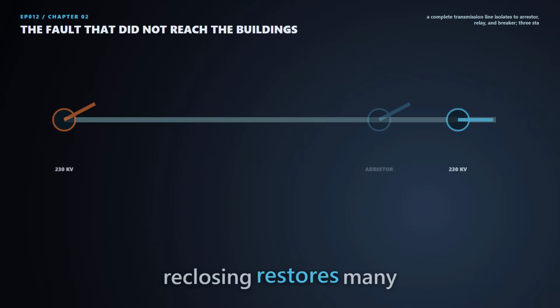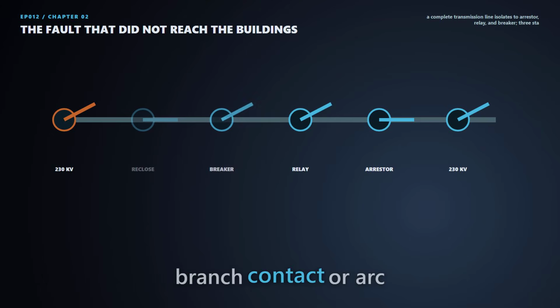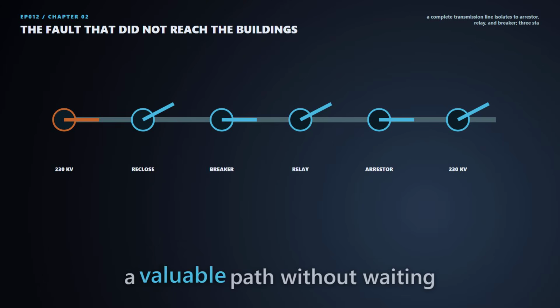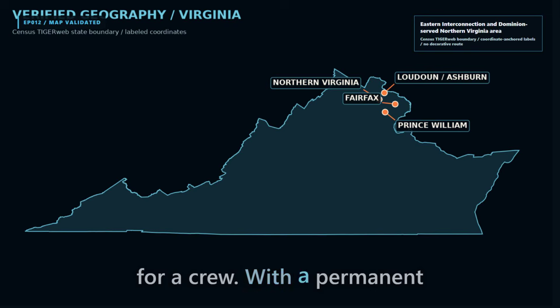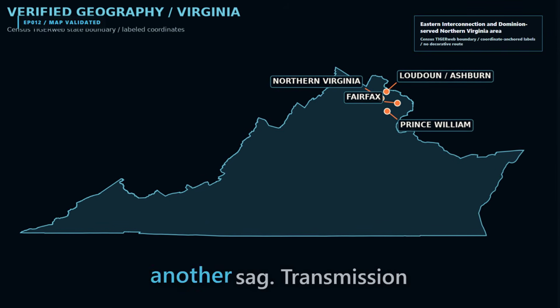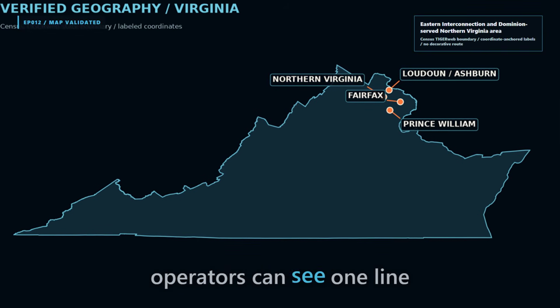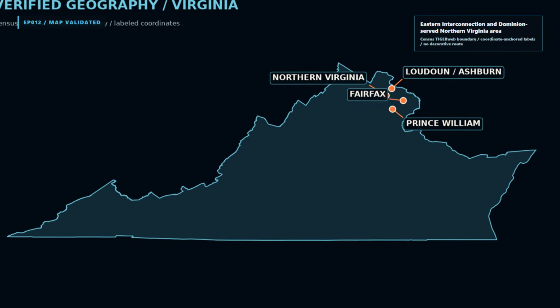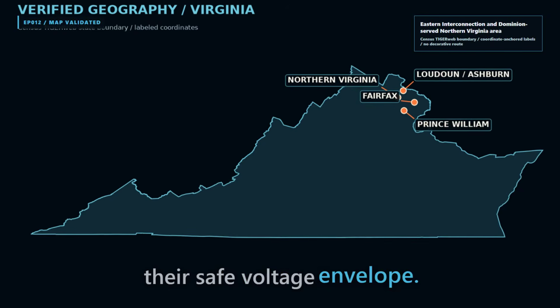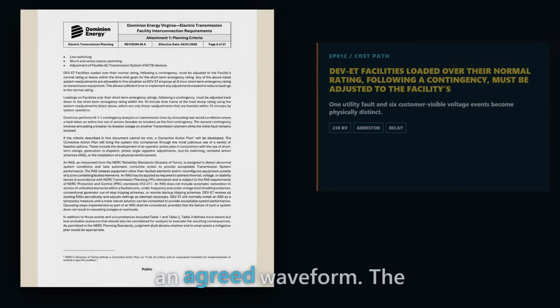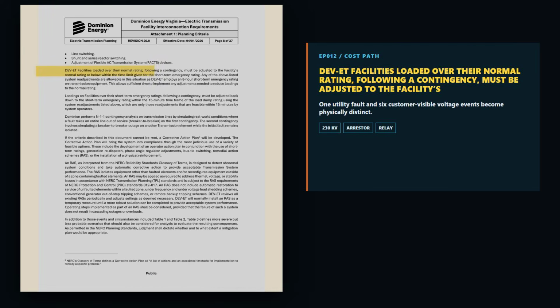Automatic reclosing restores many lines after a temporary branch contact or arc clears, preserving a valuable path without waiting for a crew. With a permanent fault, every test produces another sag. Transmission operators can see one line fault while facility controllers count several departures from their safe voltage envelope. That is why ride-through needs an agreed waveform. The campus must know the depth, duration, and normal number of attempts it should survive.